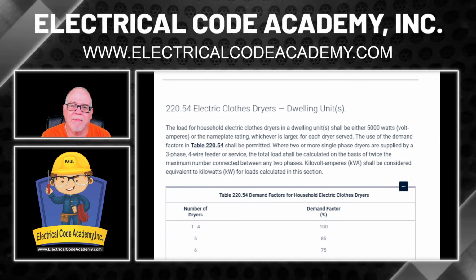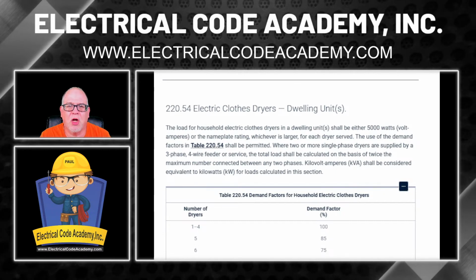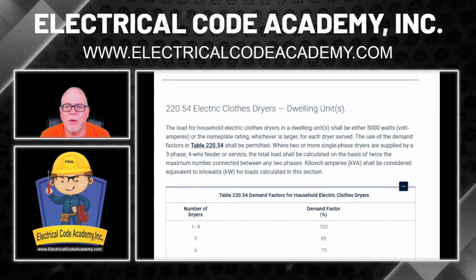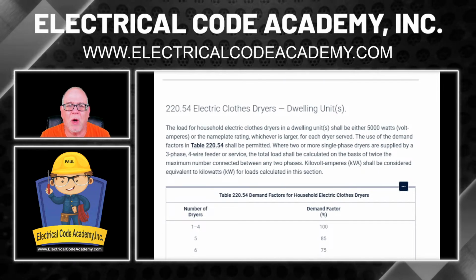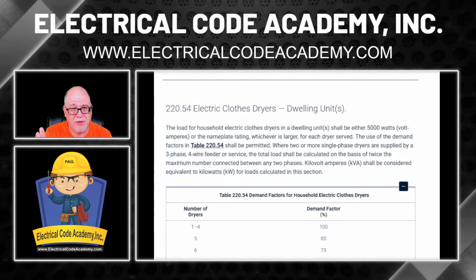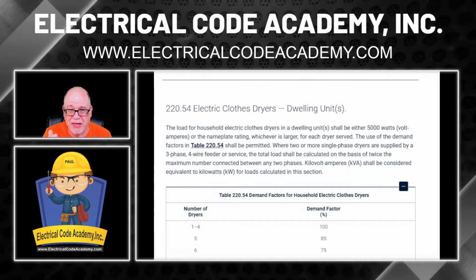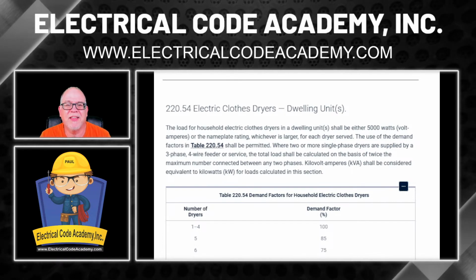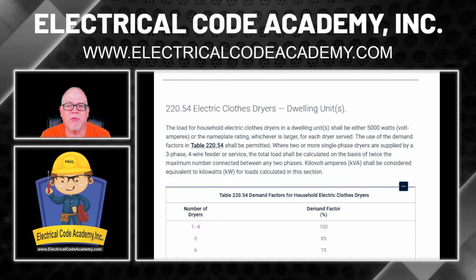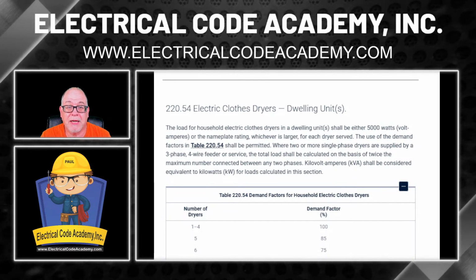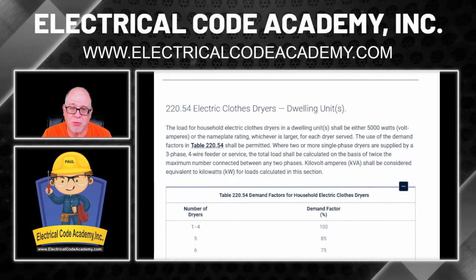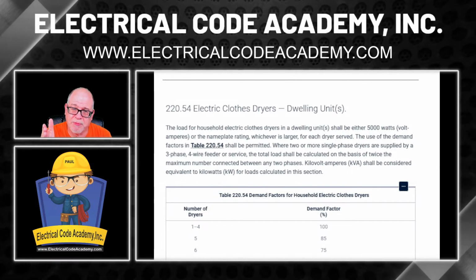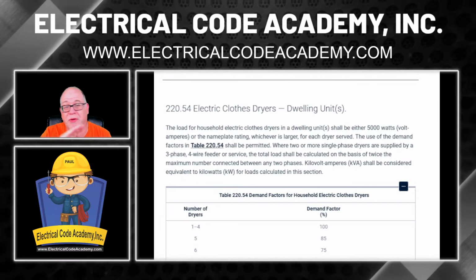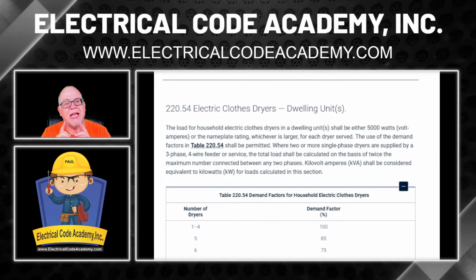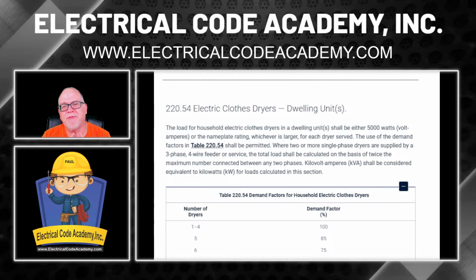All right, so look right here. 220.54. It says the load for household electric clothes dryers in a dwelling unit, or units, we only have one we're dealing with right here, shall be either 5,000 watts, and obviously you see it says volt amperes. It's synonymous, 5,000 watts or 5,000 VA, or the nameplate rating, whichever is larger for each dryer served. Okay, now we don't even need to use the table because we only have but one, and in the table it says up to 4, it's got to be 100%. So there is no demands. You take it. Now, in our question, it was 5.4, right?